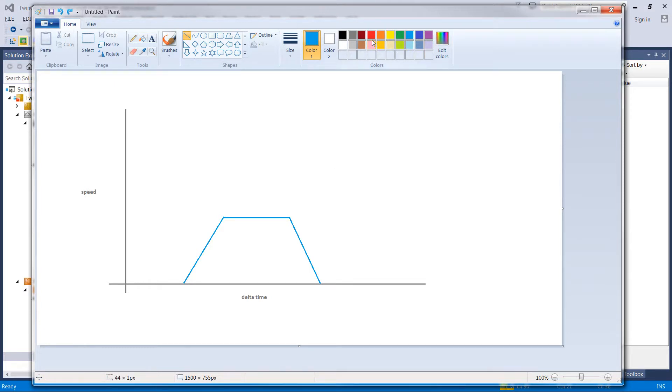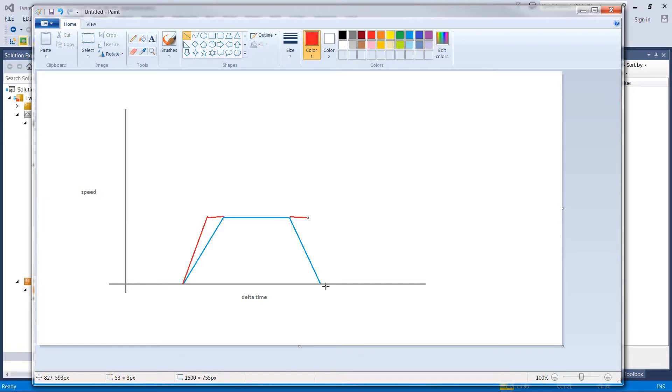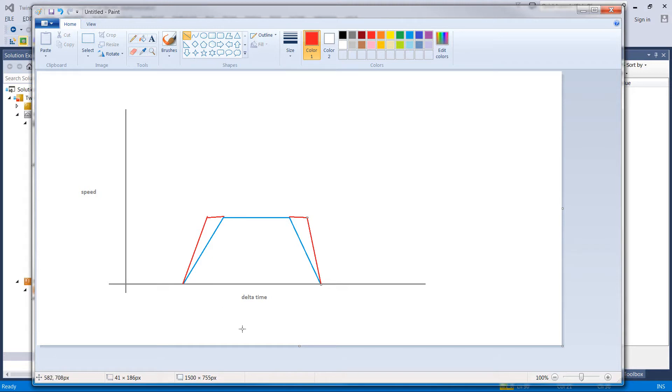Okay, so let's change some of these parameters and see what happens. So with a faster accel, say we doubled it or so, we increase its slope, and we arrive at Vmax a lot sooner in the delta time, and we end up getting to our position faster. The same goes for a quicker decel. We would do the same thing, and we would end up with an overall faster move. So you're limited, of course, by the load that you're carrying, by the power of your motor, by the following error that's okay in your system - all those sorts of things limit that.